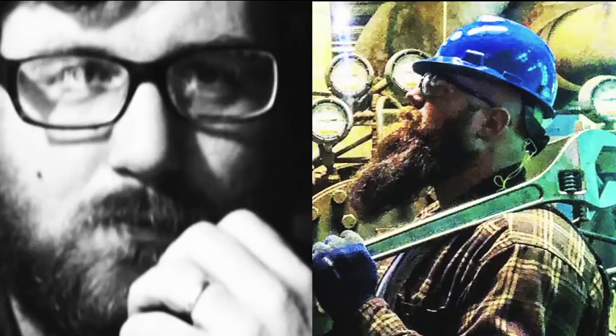Now, you talked about blockages in the actual tubing inside the chiller. How large are these tubes? You said it was rare. So how big is each tube generally? It's rare because usually you're not going to get an actual tube completely blocked. I mean, it can happen. Don't get me wrong. You can get junk that manages to get through the tower and the pump strainers and into the barrel. I've had bird skulls. I've had chunks of plastic, etc. But usually when we talk about elevated temperatures in the condenser barrel, it's going to be because the tubes haven't been brushed in a long time.